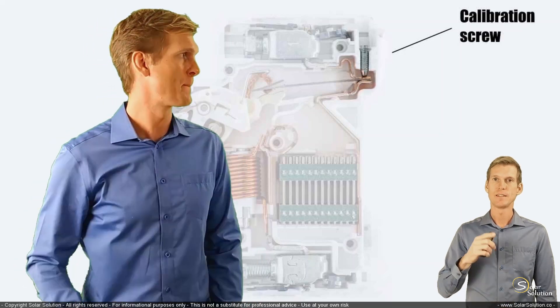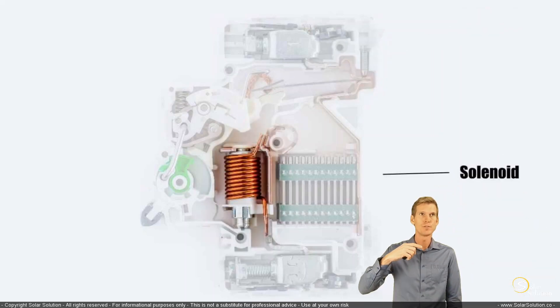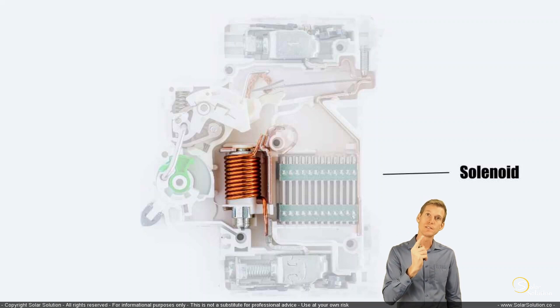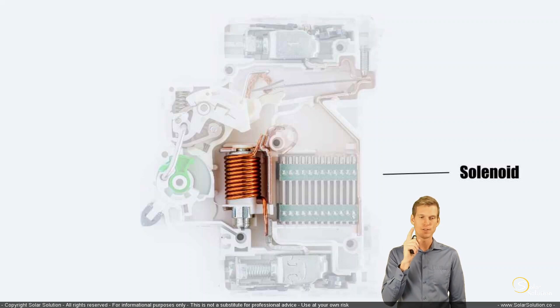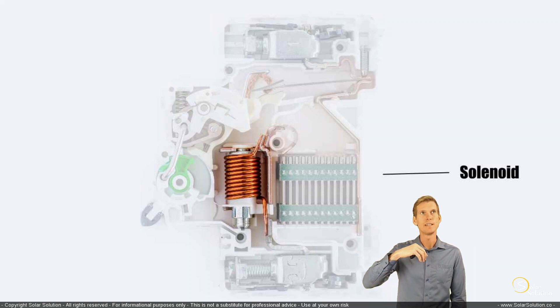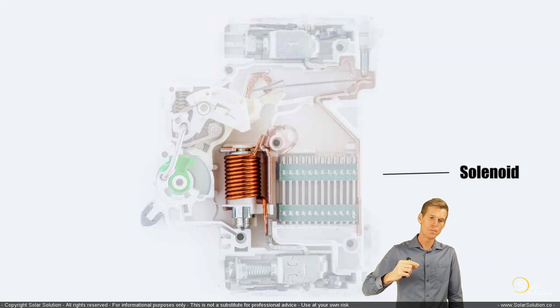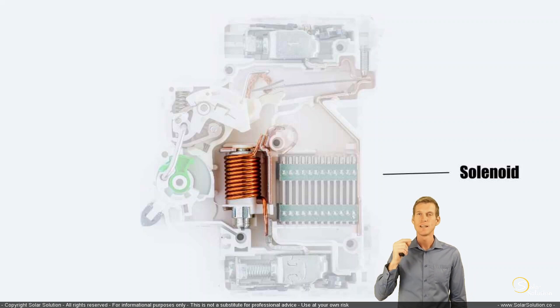That's the bimetallic strip with the calibration screw for the slow tripping current. Now let's look at the solenoid, which fulfills the function of the instantaneous tripping current. All current is fed through this coil — you can see the coil wound up there. Because there is a magnet inside the coil, if the current runs through and is above a certain value, it pushes the piece of metal inside one way, activating the lever mechanism, which then opens the contacts and interrupts the circuit.